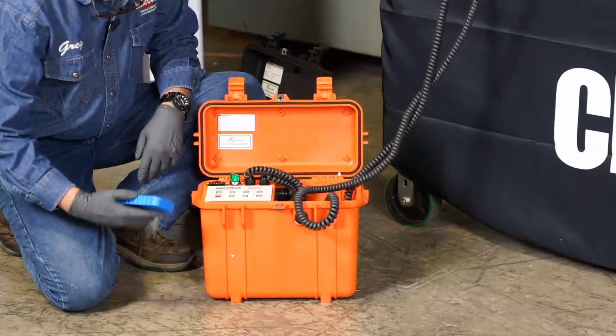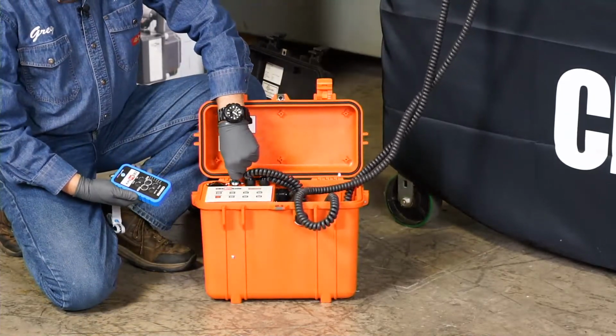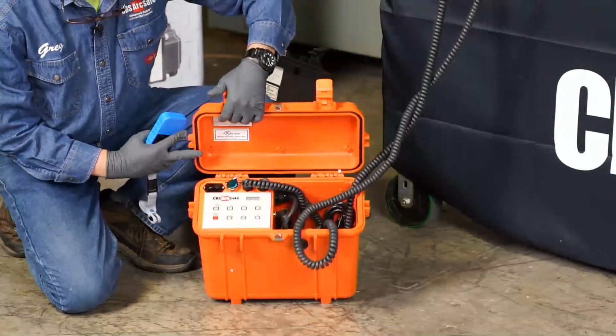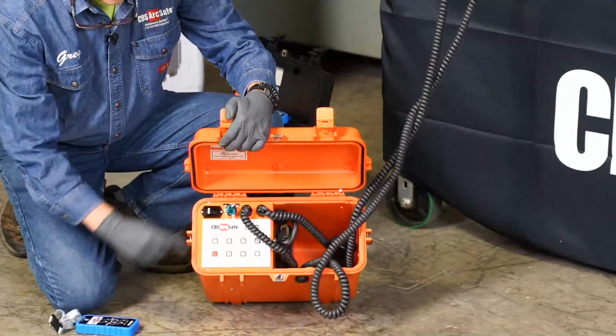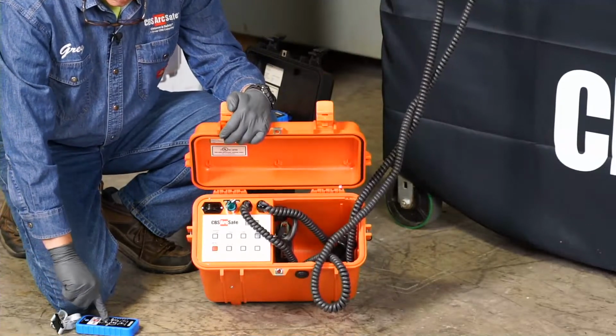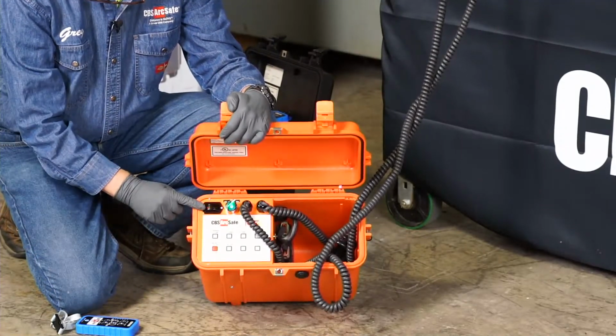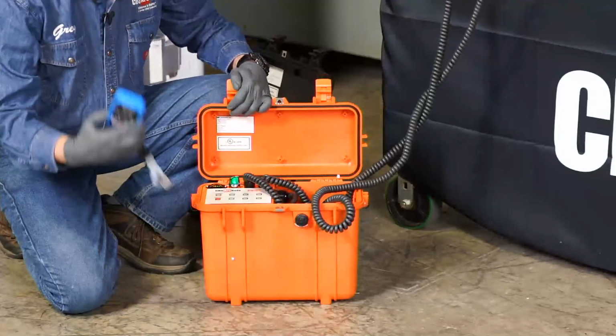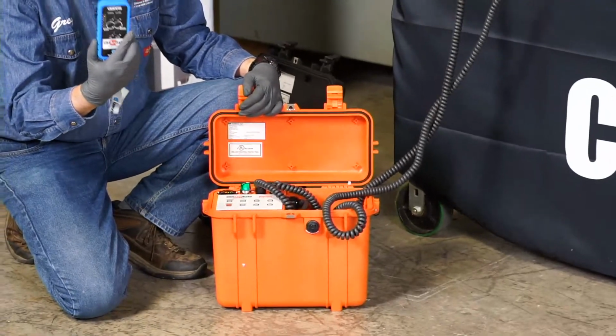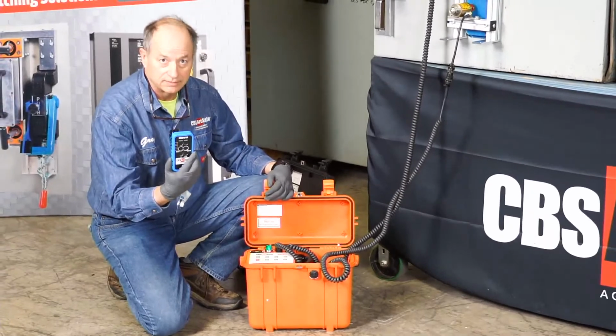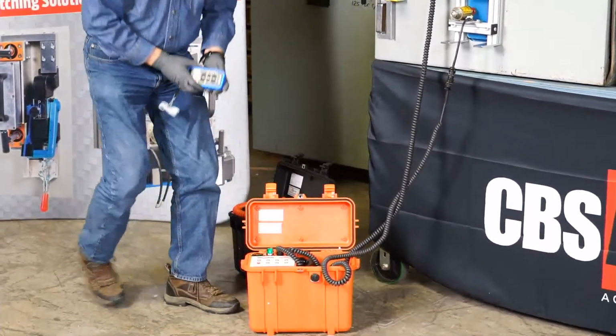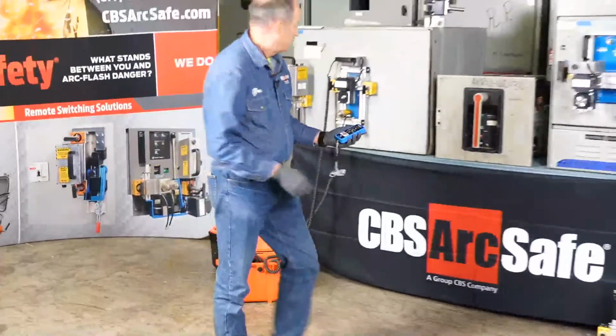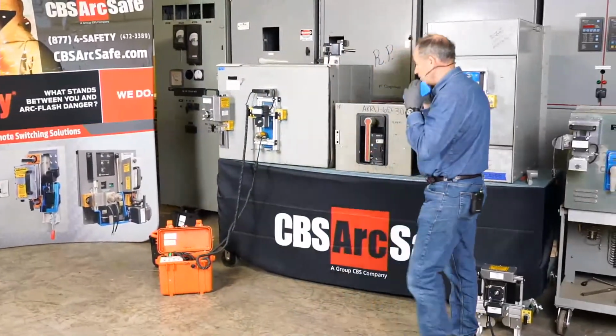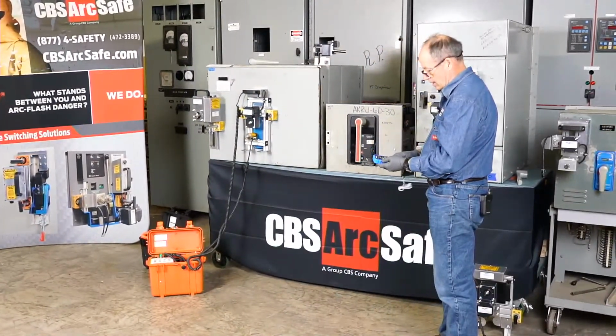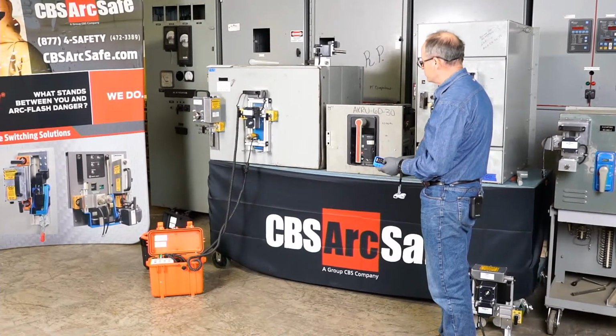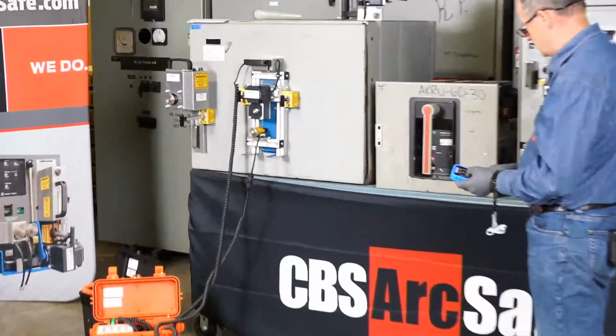Now, to be able to operate this, if we want to go to the radio remote, we're going to go to remote on here, and I'm just going to turn the box over, and you can see that I've gone to remote, and then I hit the on button, and you'll see it comes back on. Now, this is where I can operate this from 100 meters away with wireless. Okay, and I could step back and I'm going to hit trip first because I want to make sure the breaker's open.